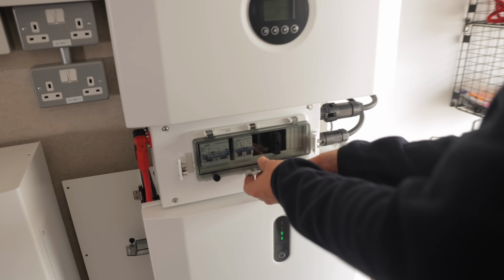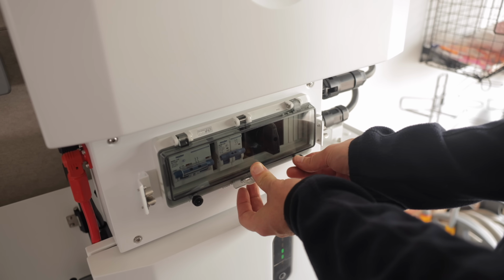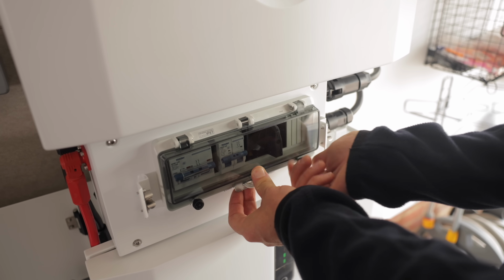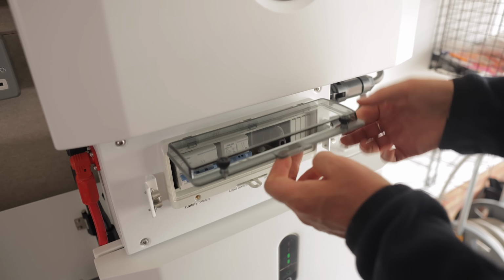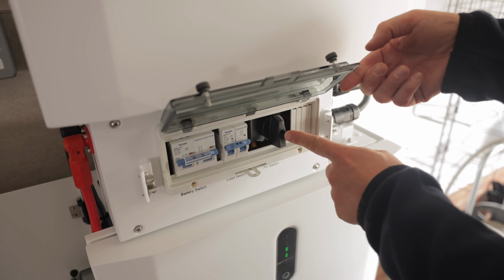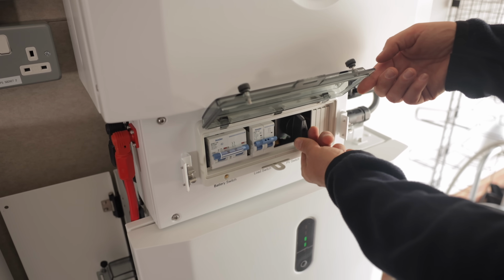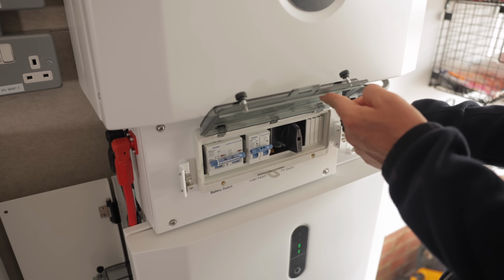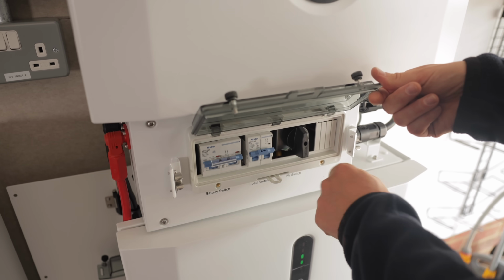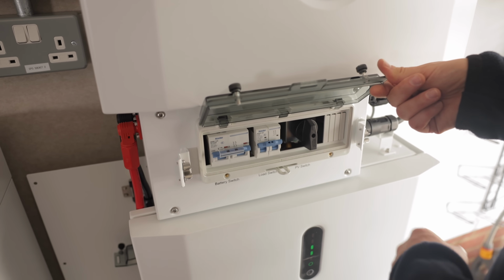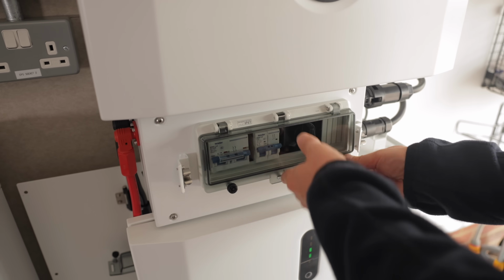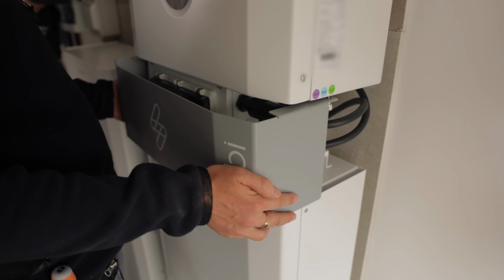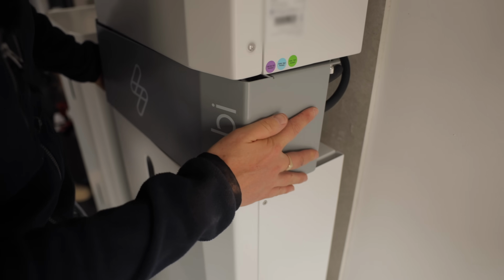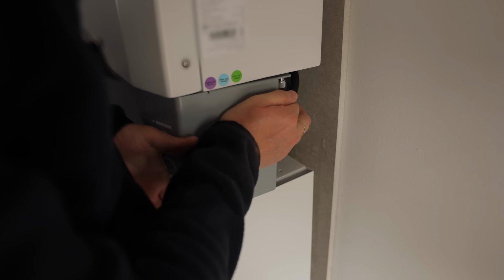There we go. We're going to close this now. That's important because that maintains the IP rating of the enclosure. This, by the way, is the PV isolator, so that's the DC isolator. If you've got solar panels connected directly into the MC4 inputs on the side here, you would turn that one on. That's the first step, but we've obviously skipped that because we don't have PV connected here. Then we're going to replace this cable cover, and to do that, just tighten up these thumb screws here.